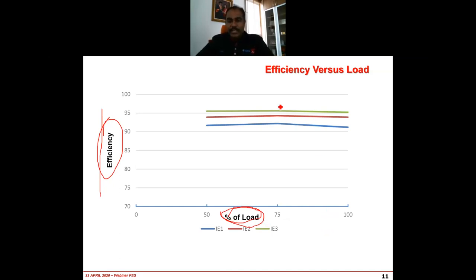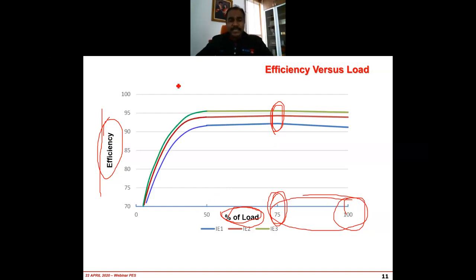If you notice, usually the optimum is about 75% of the motor, and it will be reasonably good efficiency up to the full load, okay? But then when you go below, especially when you go below 50% load, you will notice that the efficiency will start to drop, okay? Your efficiency will start to drop.